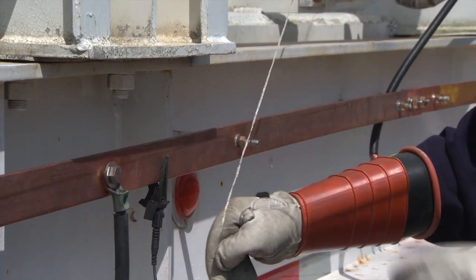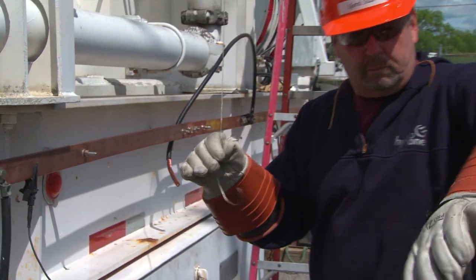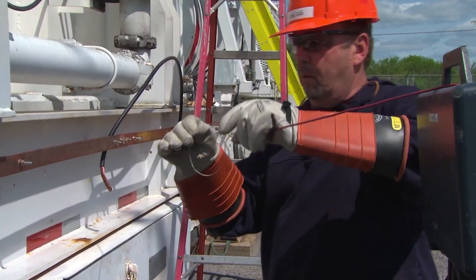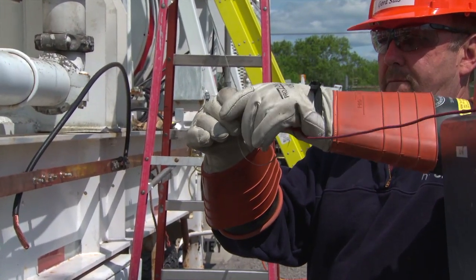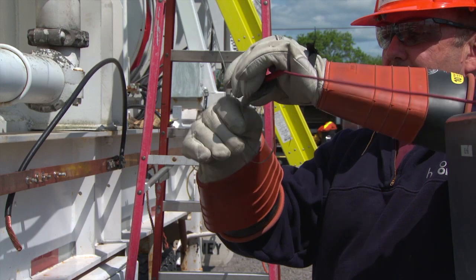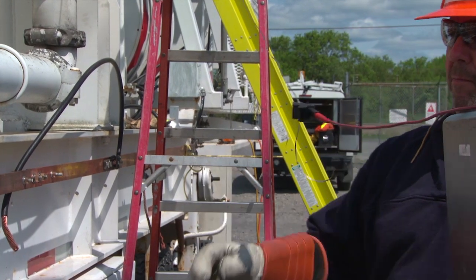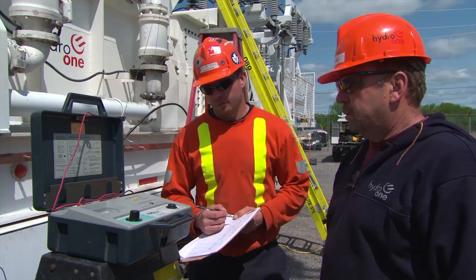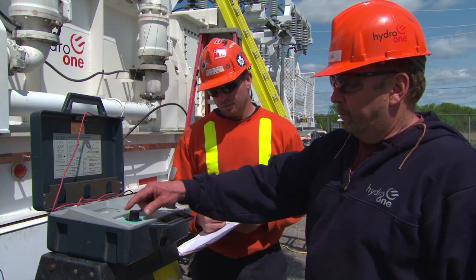Then remove the low-voltage bushing and XO winding from the ground and connect the megger lead. Ensure all employees are clear of the area and perform the low-voltage windings to grounded high-voltage test. Record test results and then ground the low-voltage bushings.